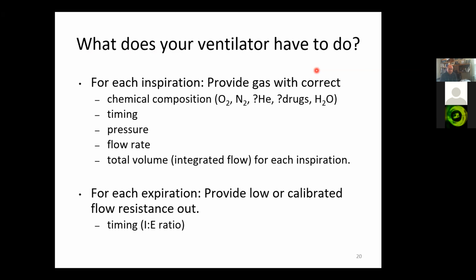So for 2 seconds, you have to get enough pressure and flow rate into the trachea, into your tube, to provide appropriate volume. What's appropriate volume? Typical numbers are about 10 cc per kilo of body mass. I have a mass of about 70 kilo, so I need about 700 cc in 2 seconds for each breath. It's a remarkable amount of flow that's required. Yes, a little less than a liter. I haven't done this for a little while, so I want to make sure this is working out.